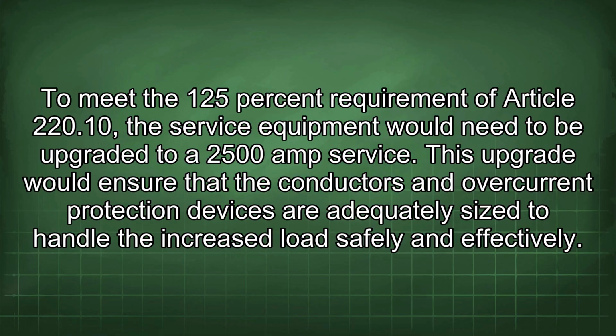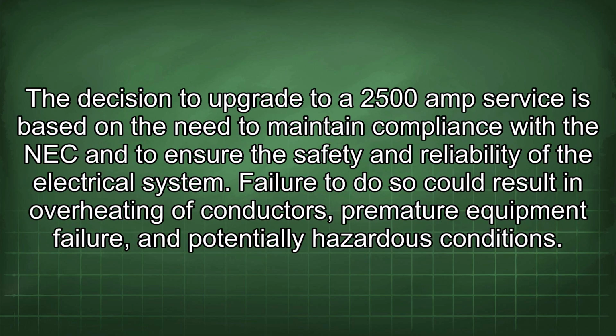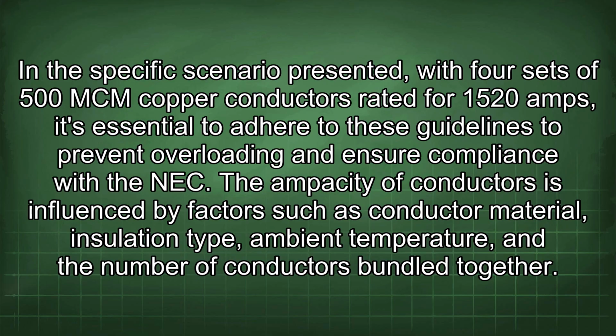safely and effectively. The decision to upgrade to a 2500 amp service is based on the need to maintain compliance with the NEC and to ensure the safety and reliability of the electrical system. Failure to do so could result in overheating of conductors, premature equipment failure, and potentially hazardous conditions. In this specific scenario presented, with 4 sets of 500 MCM copper conductors rated for 1520 amps, it's essential to adhere to these guidelines to prevent overloading and ensure compliance with the NEC.